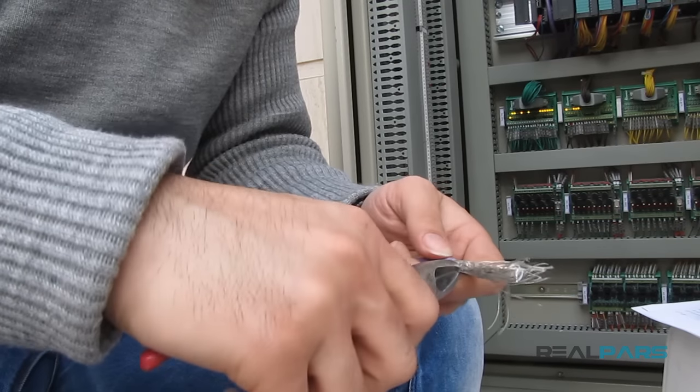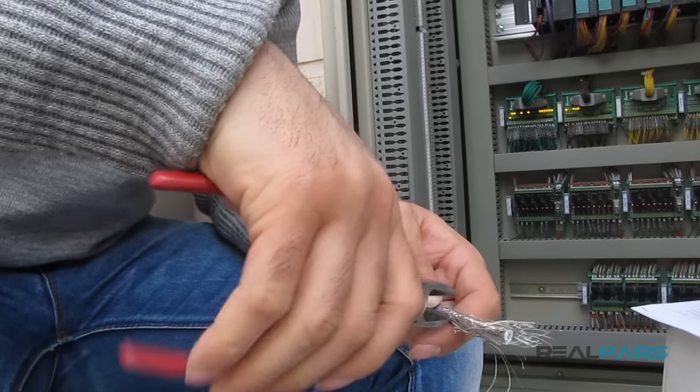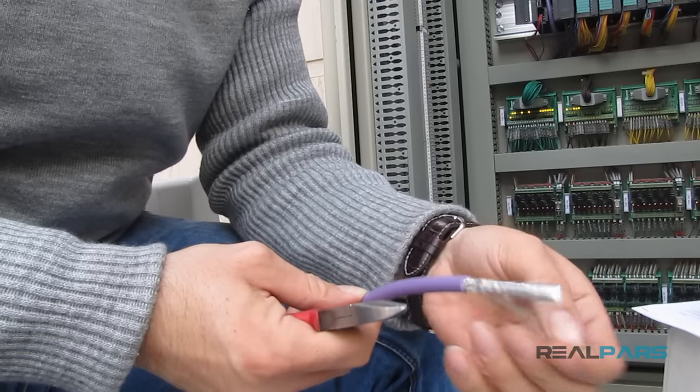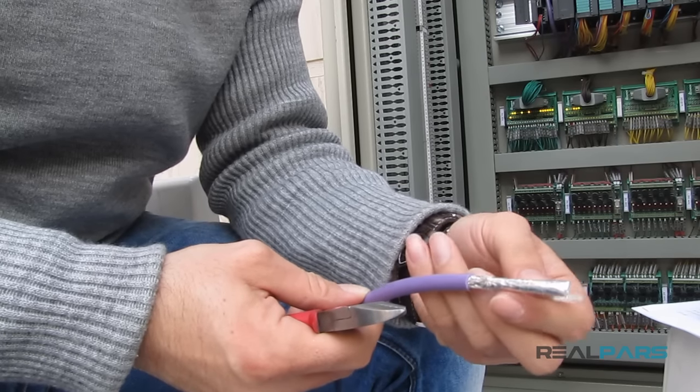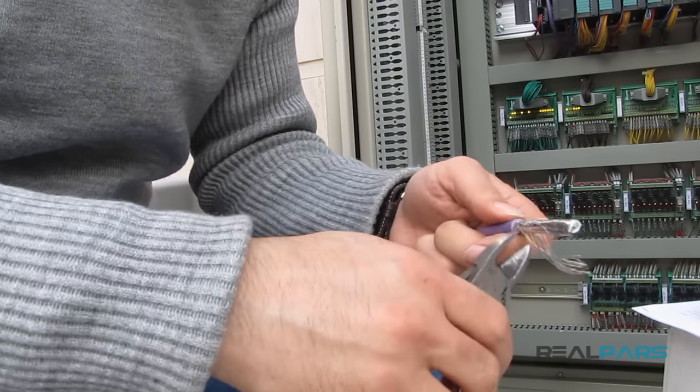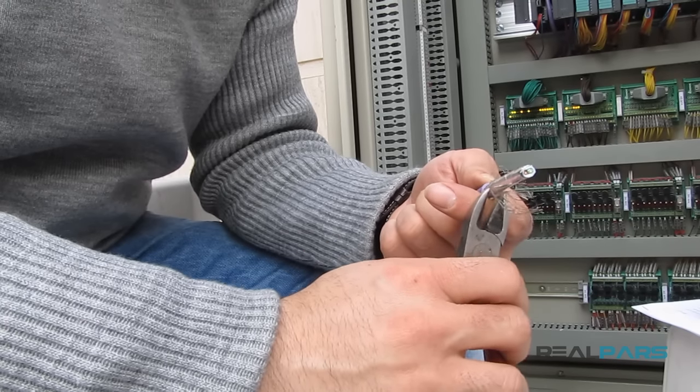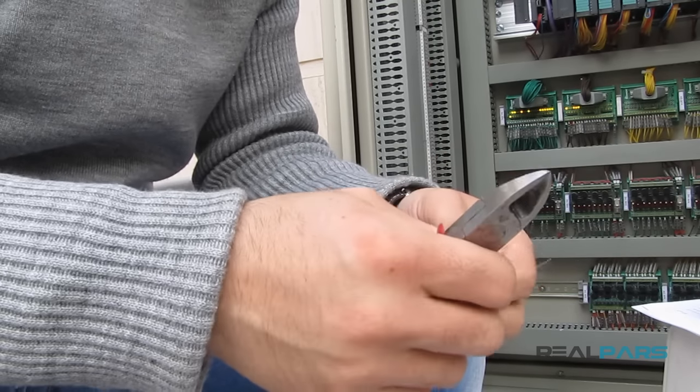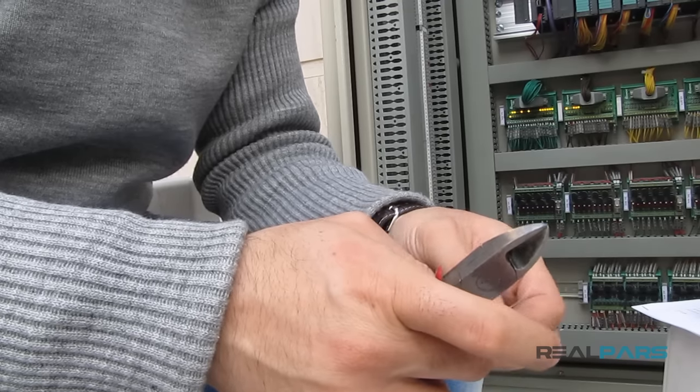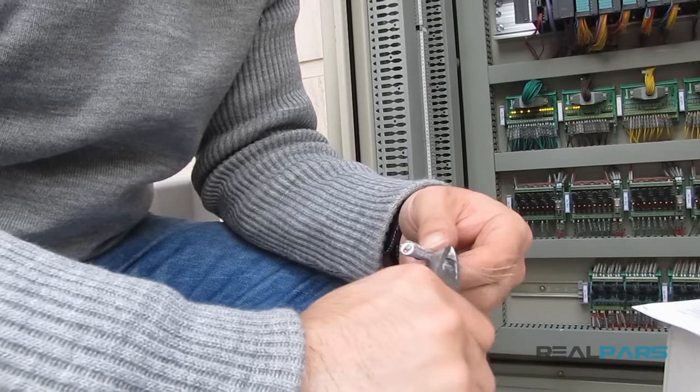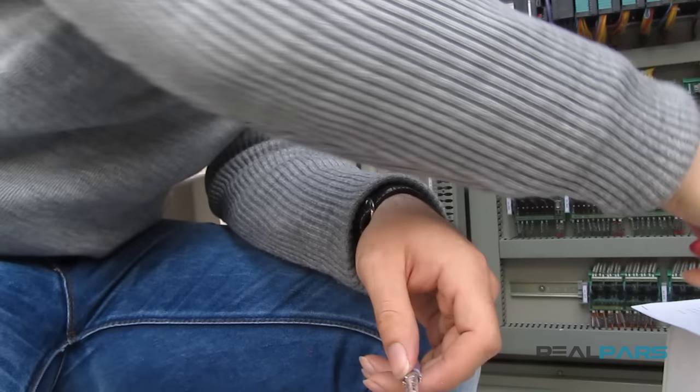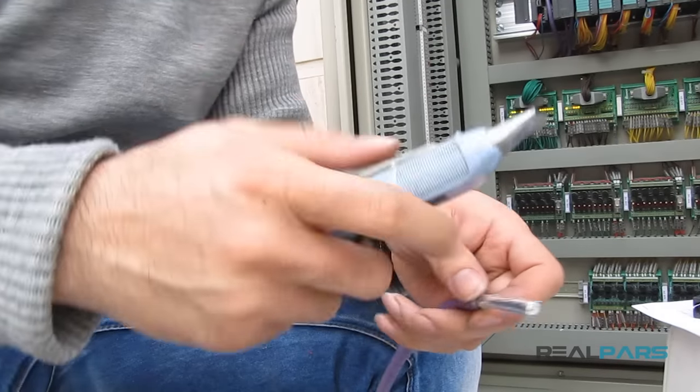In order to remove this layer, I'll use the wire cutters and begin clipping the braid at the cut end. Once a small section of the braid has been clipped, it may be easier to gather the remaining braid to clip it near the stripped end piece. Continue to clip the braid all the way around the cable until you've removed as much of the exposed braid as possible.